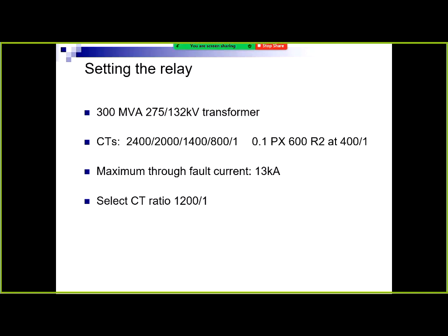If you look up at that set of CT, the CT specification, there's not actually a 1200 to 1 written up there. The way you get 1200 to 1 is between 2000 and 800 is 1200. So the actual ratios on that transformer are 400, 600, 800, 1000, 1200, 1400, 2000 and 2400. I've actually dropped that 1400 out of our specification now, but that's how you work. You get a whole lot of ratios there.